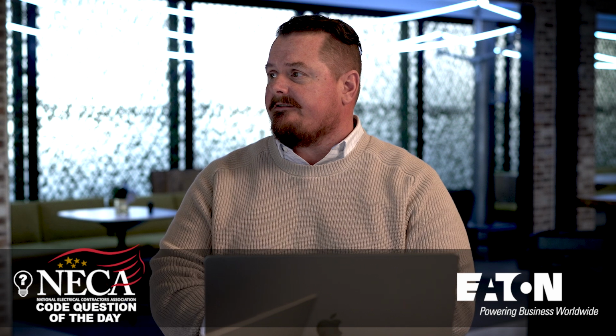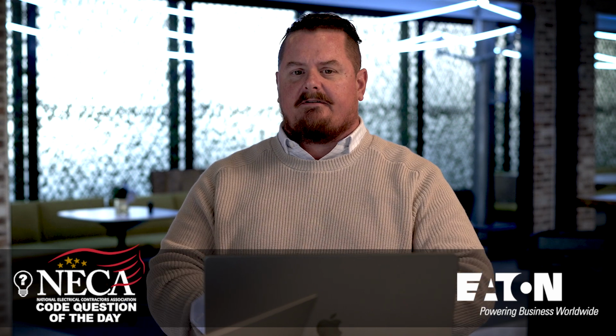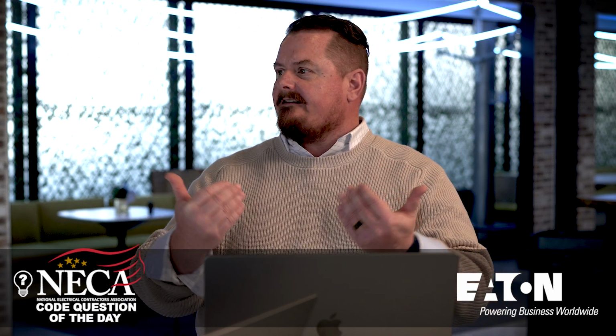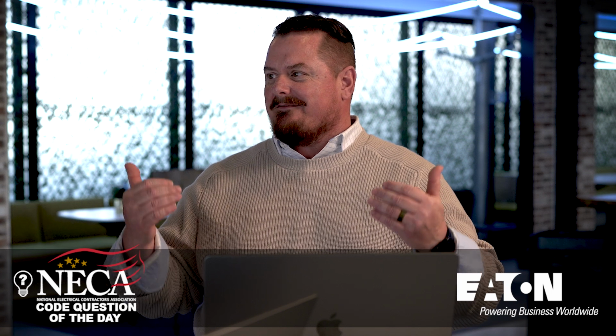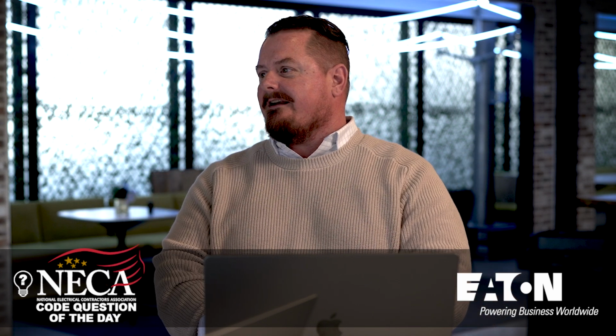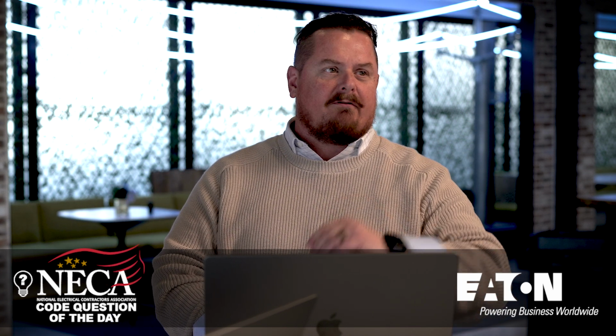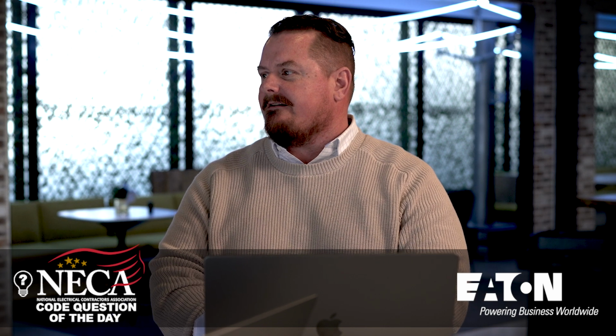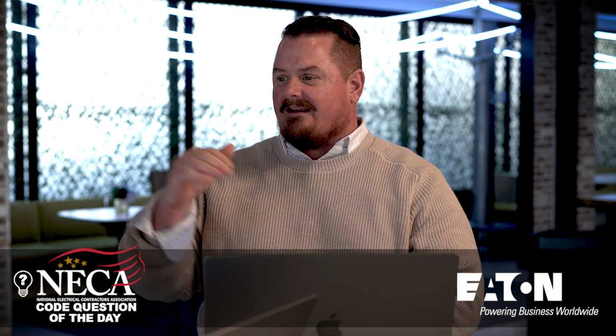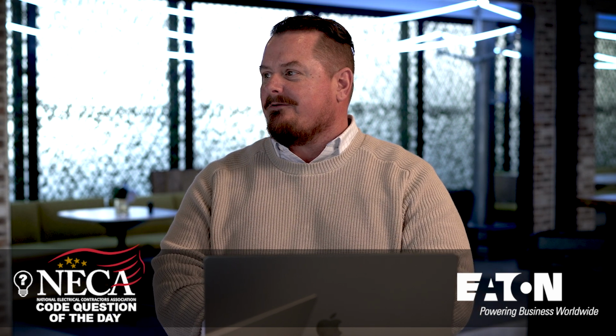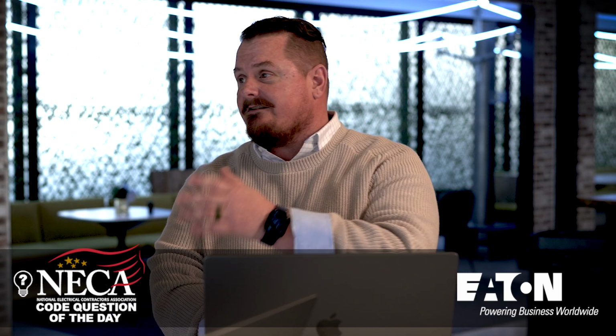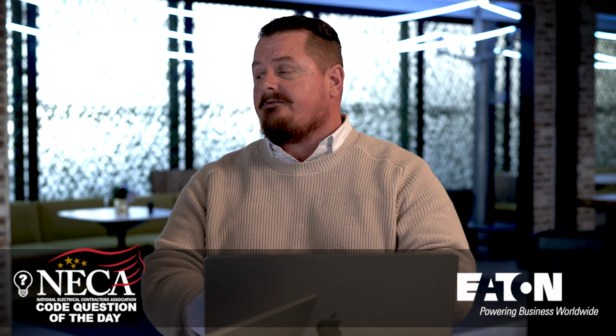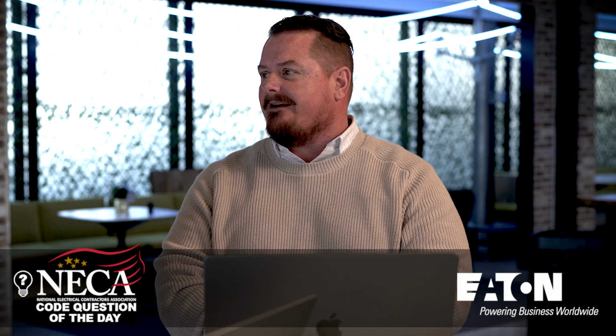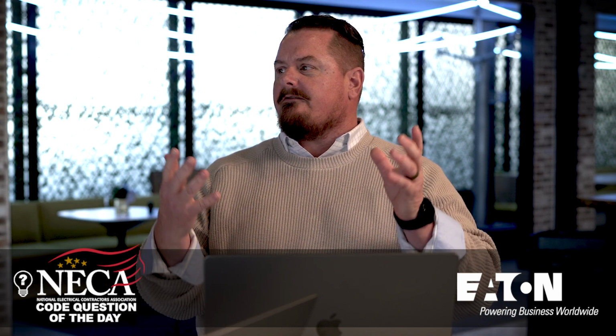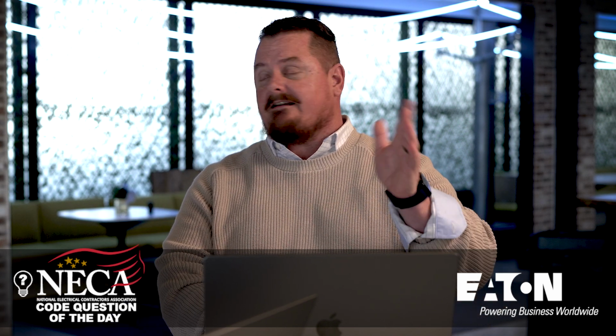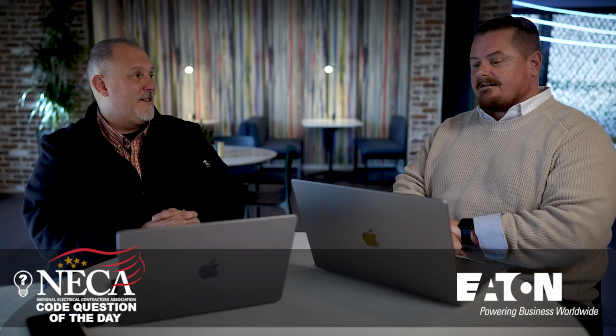Well, you just brought up what I feel is probably one of the most key issues here. In the electrical industry, we've always had this 10K threshold in our mind for short circuit current ratings or interrupting ratings. Overcurrent device, if it's not marked, what is the rating? It's 10K. So now you throw in these control panels for HVAC equipment or elevator controls or even industrial control panels where they have a 5K rating. We have to rethink that whole concept of as soon as we get to 10K, we're done, because it's not going to be adequate anymore.